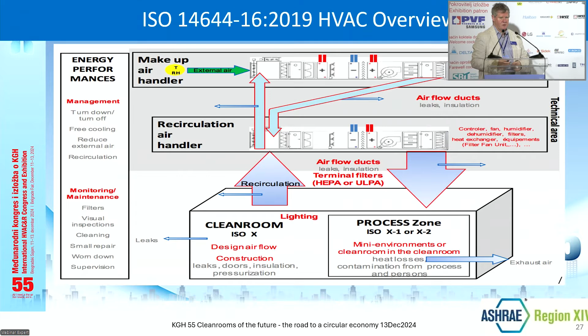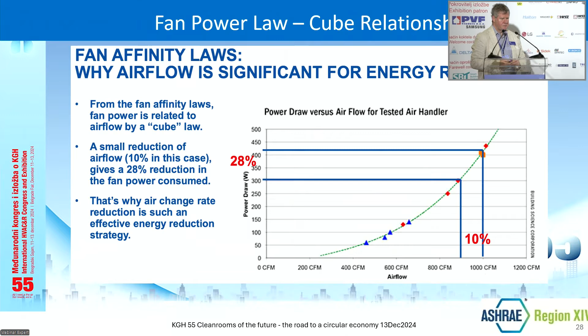Okay. One of the interesting things is the fan affinity law, that the air volume and energy are related in a cube manner. So when you reduce your air, you reduce dramatically the electrical energy consumption of the fan motors. So therefore, the secret of reducing energy in clean rooms is to use less air. We spent decades using too much air. So that's a big change in the industry to go to that.